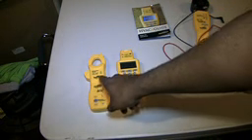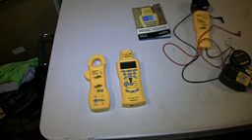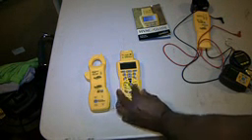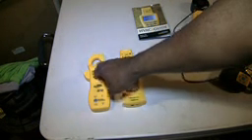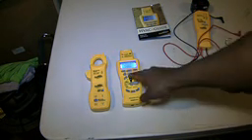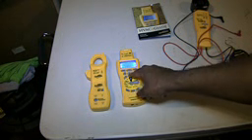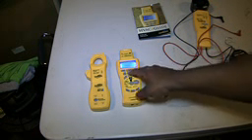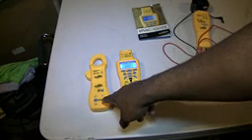So normally what I do is I put the AC clamp accessory head on top of the transmitter, and after you clamp it to the wire at the blower motor, I'll set my HVAC Guide to data logger mode, and in data logger mode it allows me to see what the amperage is doing. For the most part, I don't worry about filling in all this information right here. I just come down to start, sync it, and then I can get my amp readings from this.